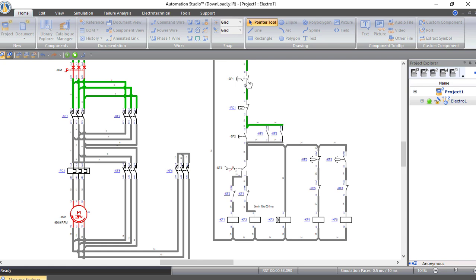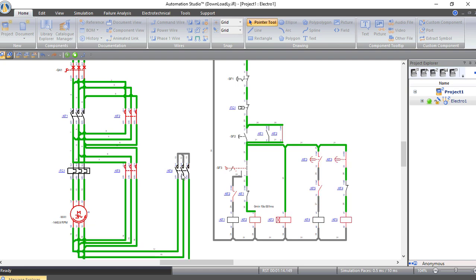To reverse the direction of the motor, let's stop it — this is the stop push button. Now let's move the switch to be connected to K2. Press start again and the motor is working on star in the reverse or anti-clockwise direction. After 10 seconds it moves from star to delta and still moves in the anti-clockwise direction.